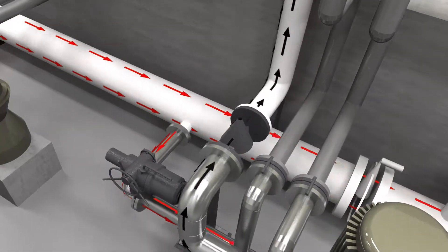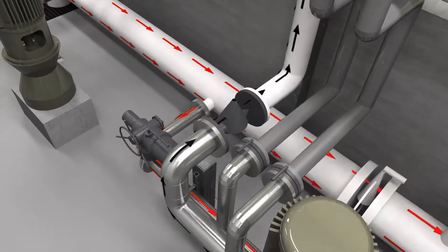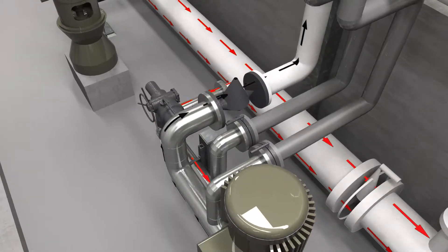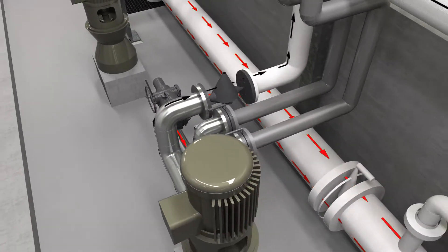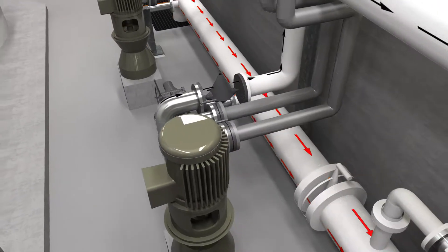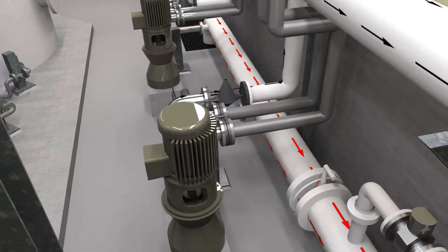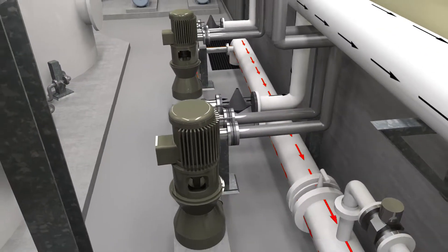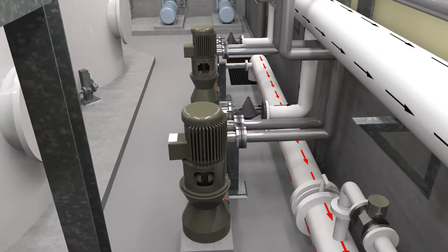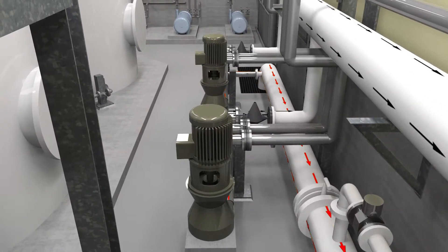With the excess pressure removed, the Chino II desalters concentrate is sent to the pellet reactors and high-rate solids contact clarifier, where it is chemically softened to remove salts, which will allow further water recovery using a subsequent secondary reverse osmosis process at the CRF.